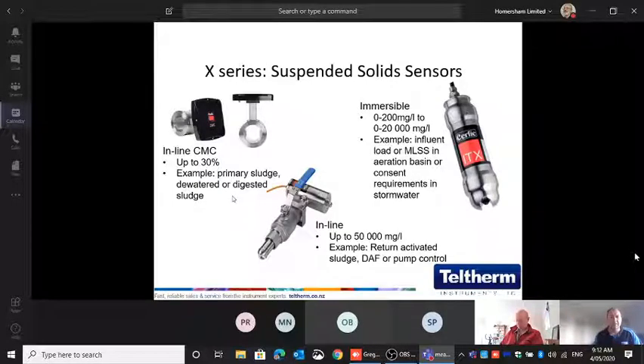Inline units go up to 5%, mainly used in return and waste activated sludge. This unit, the sensor looks the same as the sludge blanket unit. Same size, same thickness. That unit has references all over the place. Panpac is the biggest one. They've got about 6. Rangitikei District Council's got one. New Plymouth had one. They took it out because we had issues with lagoon sludge.